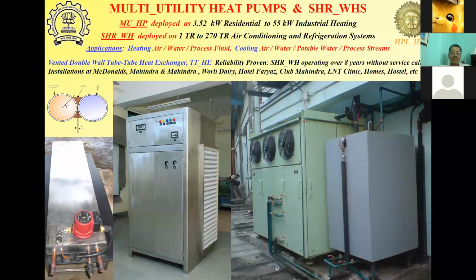Evaporative condensation reduces the requirement of air that needs to be passed through this, because the air is not sensibly heating, but it is evaporating water into it, and thus the quantity of air required is less. The reduced quantity of air in this particular case enabled us to reduce the airflow rate, and the pressure drop was much lower in this particular unit. So the total power consumed by the fans in this unit for a 24-ton system was around 9 times less than the power consumed by a conventional air-cooled condenser fan for a similar size unit.